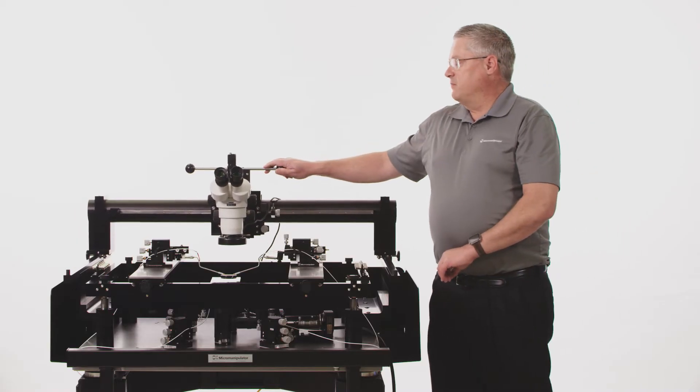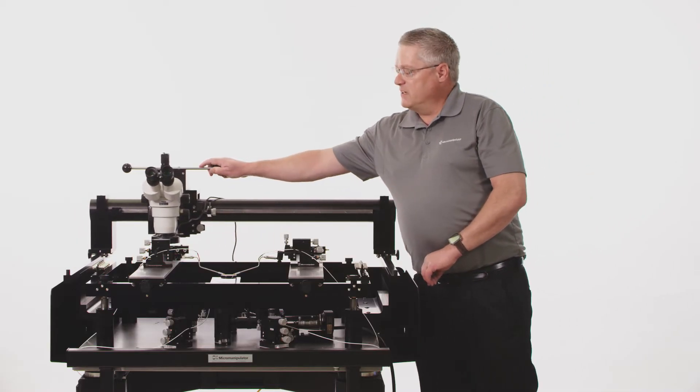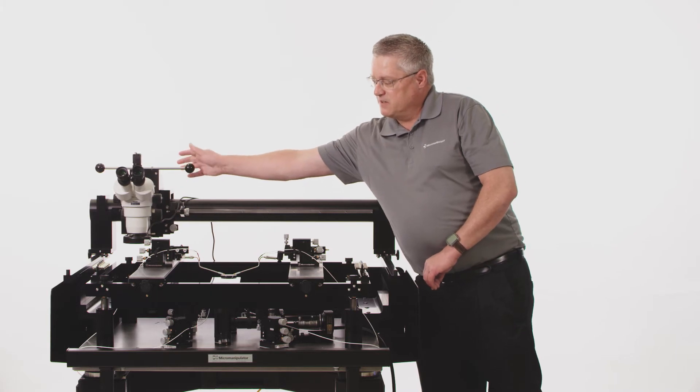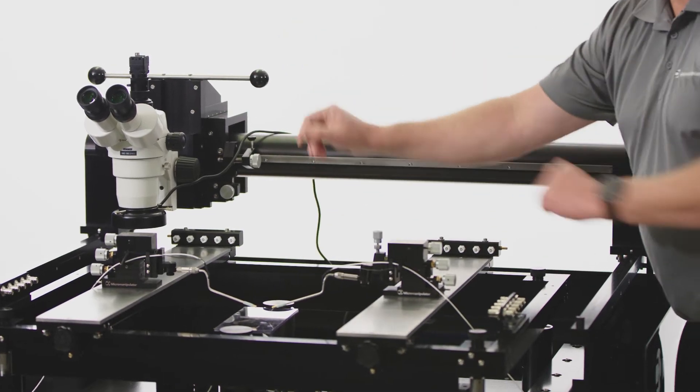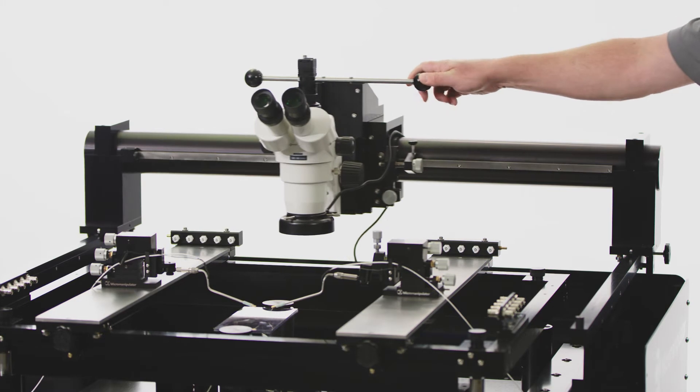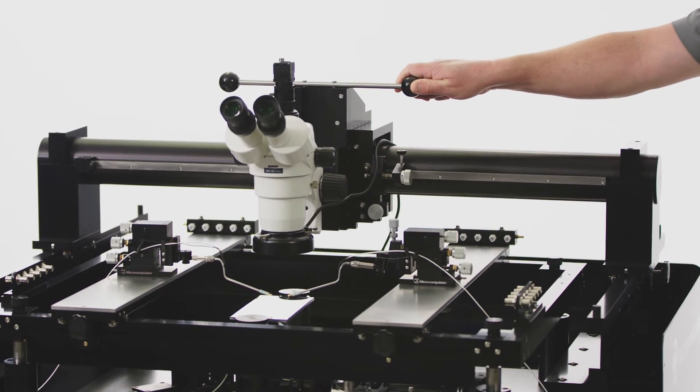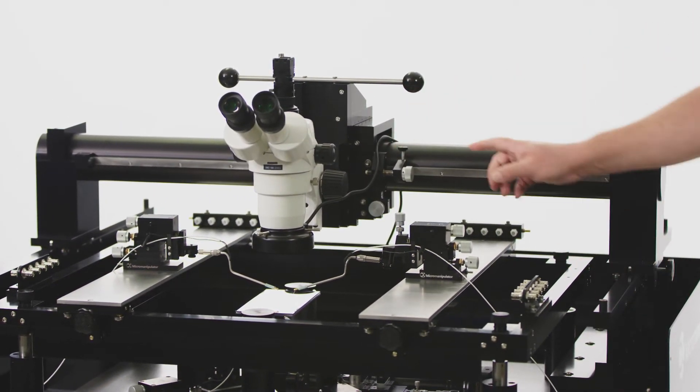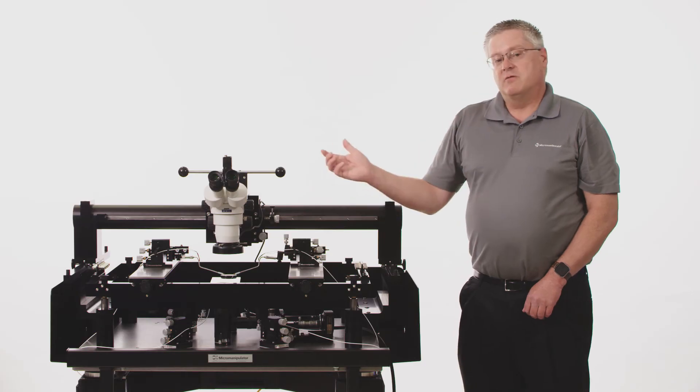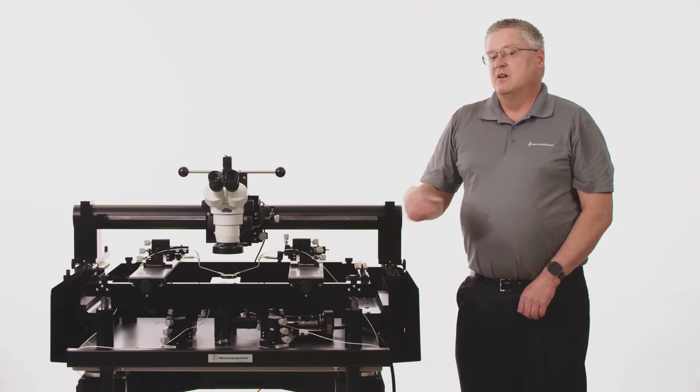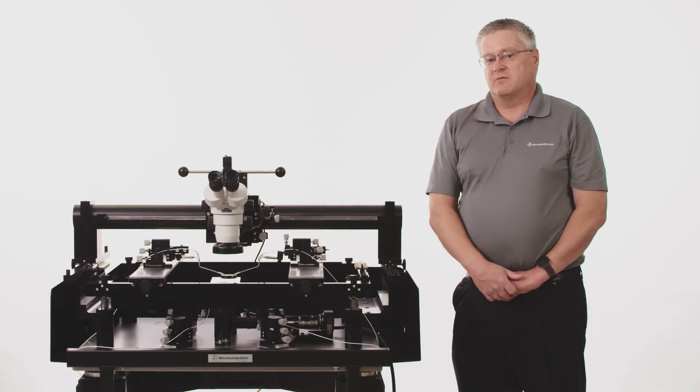It does that by introducing a new approach to microscope motion. The Versa microscope can be completely moved out of the way 26 inches by 26 inches of motion so that you can set up your system. When you're done setting up, move it back into place, lock it down, and then you have fine controls just like you would have on a regular wafer probe station for your focusing and for your fine XY motion.